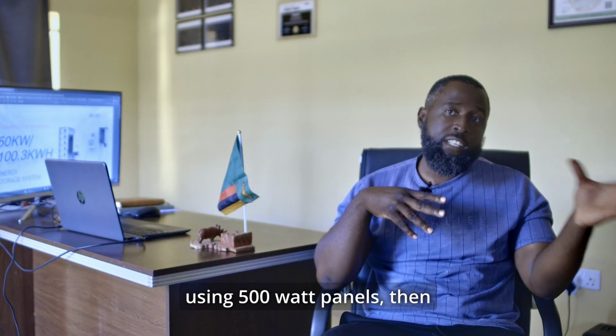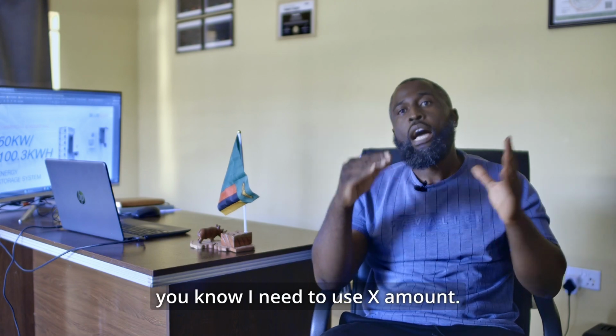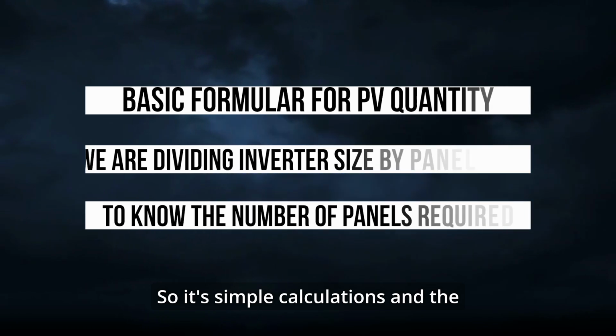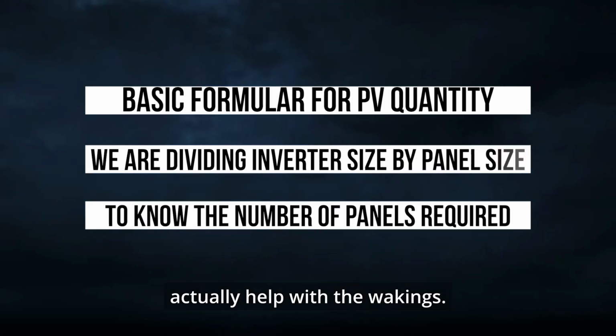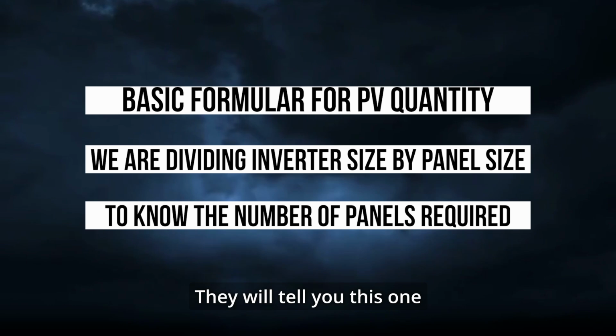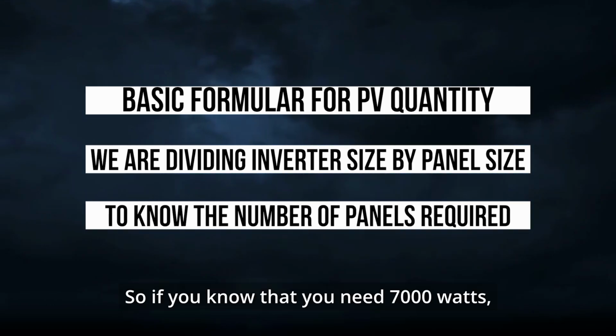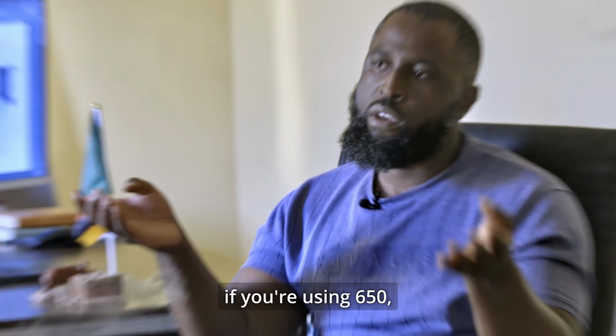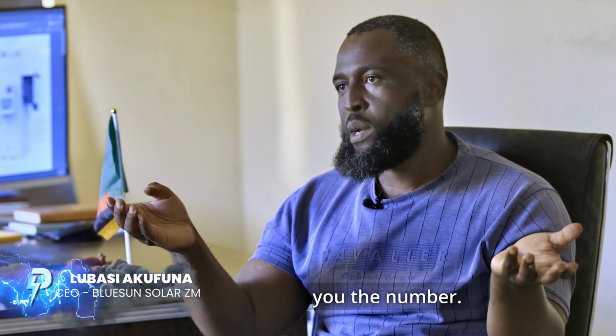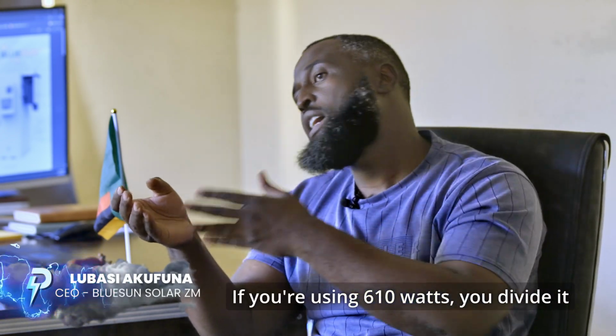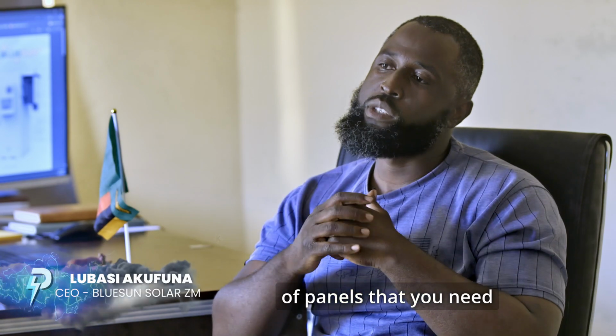If you're using 500 watt panels, then you know you need to use X amount. It's simple calculations, and the manufacturer actually helps with the workings, telling you this one needs X amount of power. So if you know you need 7,000 watts, and you're using 650 watt panels, you divide to get the number. If using 610 watt panels, you divide to get the number of panels you need for this to work.